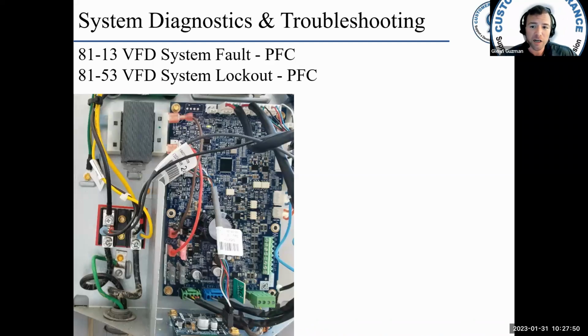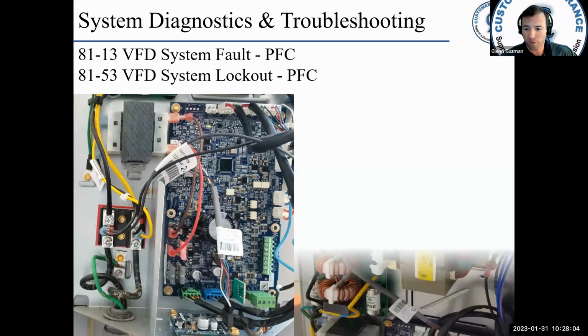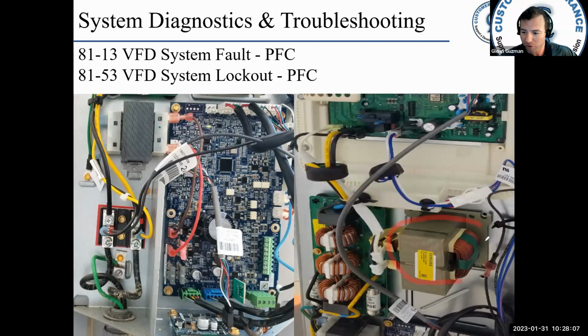Okay, continuing with the PFC, 8113, 8153. PFC, by the way, is power factor correction. There are power factor correction circuits, and they involve the reactors. Here you can see a reactor on this unit. Okay, the 5-ton units have 2 reactors, but I've seen cases where these plugs get loose, and you will begin to have some of these PFC faults. Okay, if you have those faults, then check your reactor, check the plugs. Okay, these plugs, the other end, follow it up to the VFD, make sure that's a sound connection there.